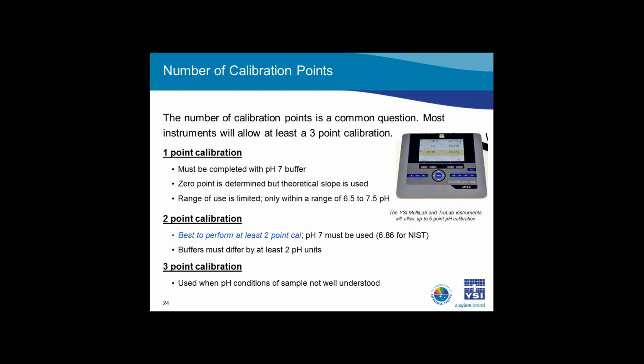Sometimes, depending on the instrument, the order you calibrate is important. Older instruments require you to start with buffer 7. Newer instruments allow you to calibrate in any order and calculate the intercept and slope after the calibration is complete. Just check with the instrument's operating manual to make sure you are following the manufacturer's recommended procedure.